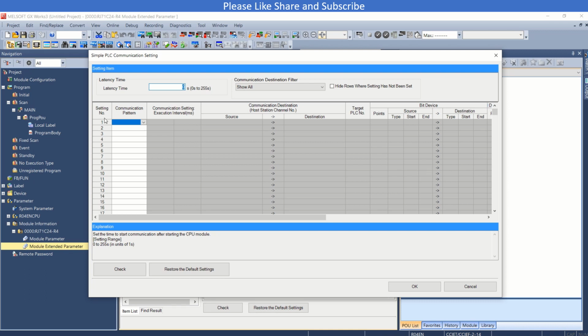So the first setting, number 1, is the communication pattern. We have two communication patterns, one is read and one is write. So we will be using read here. Of course, we know what read and write mean. And for the communication setting, we have two here, that is fixed interval and the other is on request. So I am using the fixed interval first, and the value of the gap is 100 milliseconds. You can increase or decrease this as per your requirement.